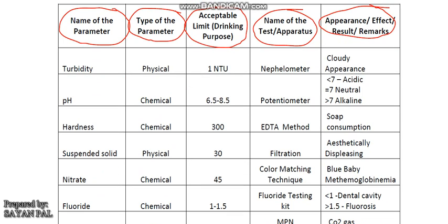First, turbidity. It is a physical water quality parameter and it is measured by nephelometer; the unit is nephelometric turbidity unit (NTU). The acceptable limit is 1 NTU and its cause-for-rejection limit is 10 NTU. Because of turbidity, water looks cloudy — that is, cloudy appearance.